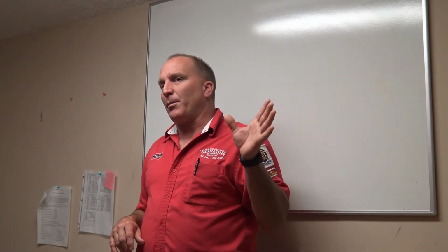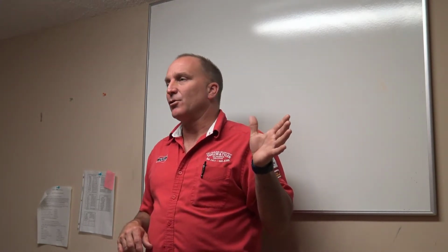Now, Mitch went out to a job, and I'm looking at his gauges and I'm going, there's no way that these pressures are this messed up. So I went out there with him on the system and we put gauges on the system, and they were completely different pressures. Now, if he wouldn't have taken a picture of these gauges, there's no way I would have believed him that he was running a 410-pound head pressure with whatever, okay?